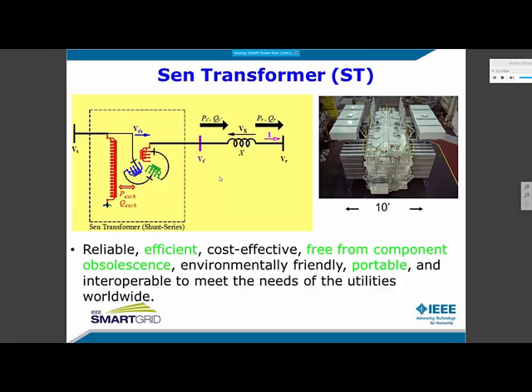The side effect of impedance regulation, as I mentioned earlier, in the case of ST, is naturally built into the power circuit. The exchange of PQ flows both ways between the shunt unit and series unit is already there. Unlike in a UPFC, we don't need another inverter. If we have a specific need for a voltage regulator, just as an auto transformer, ST can do that. If we need an impedance regulator, as in a UPFC, ST can do that too.